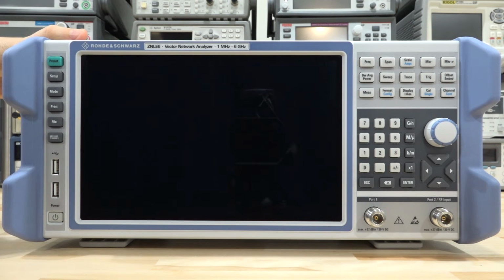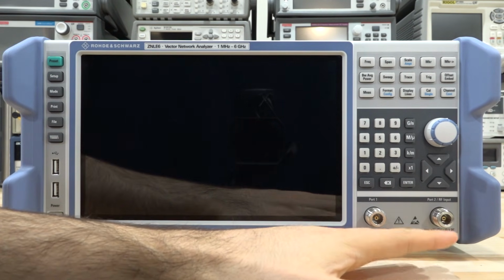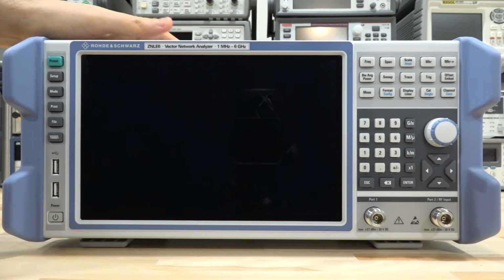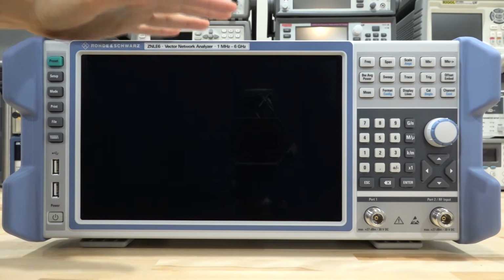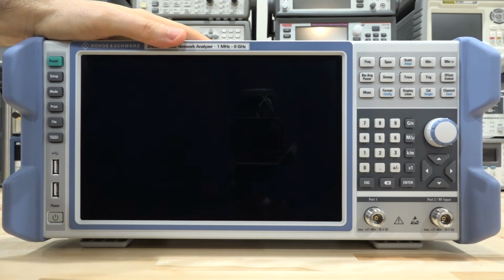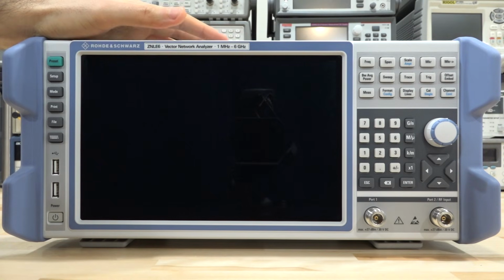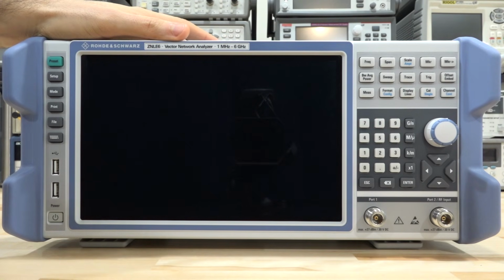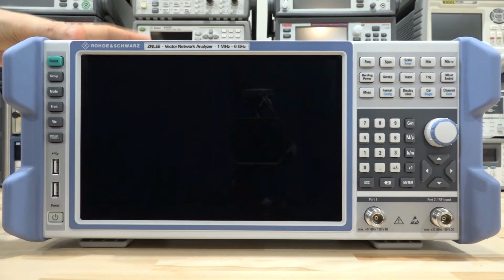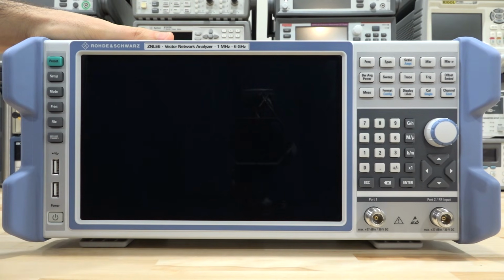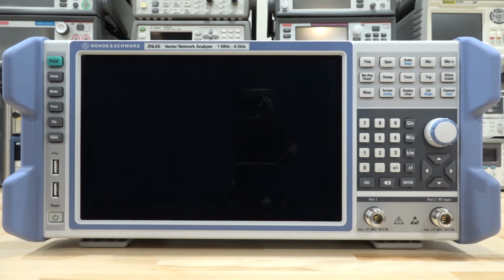And the reason is because once you have the unit calibrated and the cables coming from the front panel, you don't want to have to move the cables a lot, which means you would want to have this at the back of the desk sitting in front of you. And the less you need to move it around, the more space you have in front of it, the better it is. And this is why they have spent so much time making sure the depth of the unit is manageable. And this is going to be very handy once we do our calibration and our measurements here as well. So let's take a look and see what's at the back of the unit.